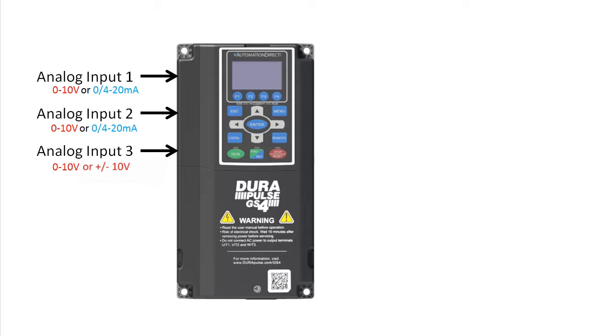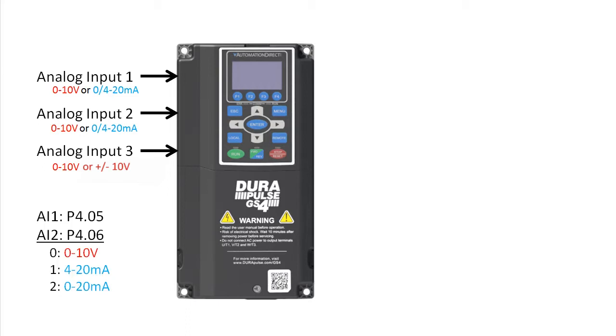When analog inputs 1 or 2 are switched to current mode, these parameters allow you to switch between 0 to 20 milliamps and 4 to 20 milliamps.